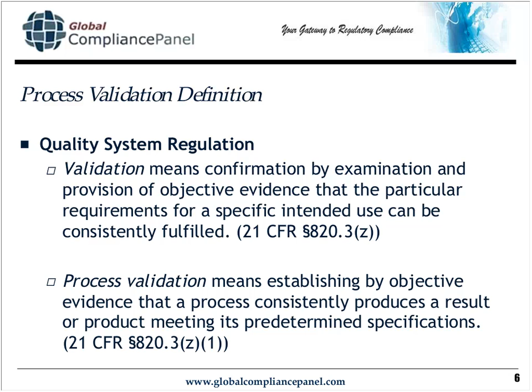Well, in QSR, it says when the results of a process cannot be fully verified by subsequent inspection and test, then the process has to be validated. Now, fully verified is not a defined term, and it causes a lot of grief about exactly what it means, and we'll show that in some of the warning letters that we're going to look at. Now, in 13485, it turns out that 13485 and ISO 9001, the wording is identical. So we'll just talk about 13485 because we're in the medical device context here. I need to validate any process for production and service provision where the resulting output, right, so the output of a process is a product, cannot be verified by subsequent monitoring and measurement.